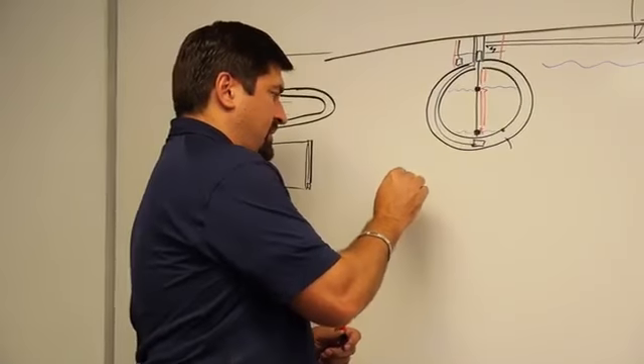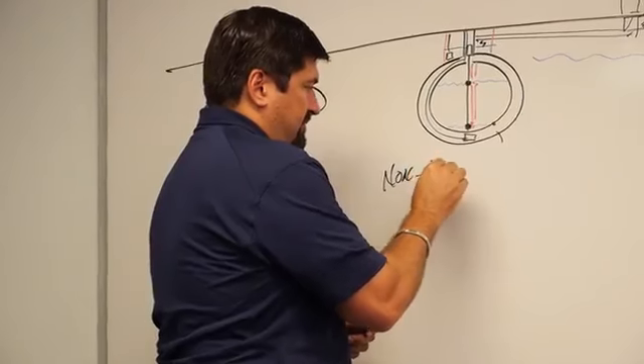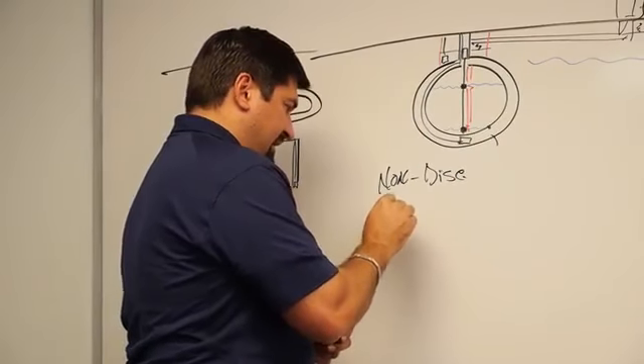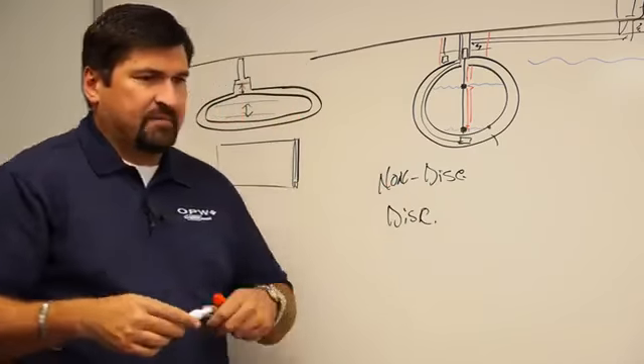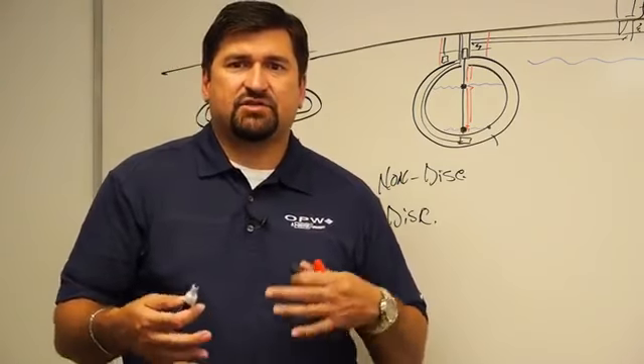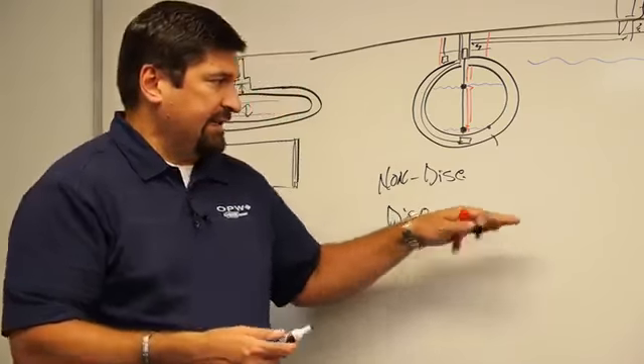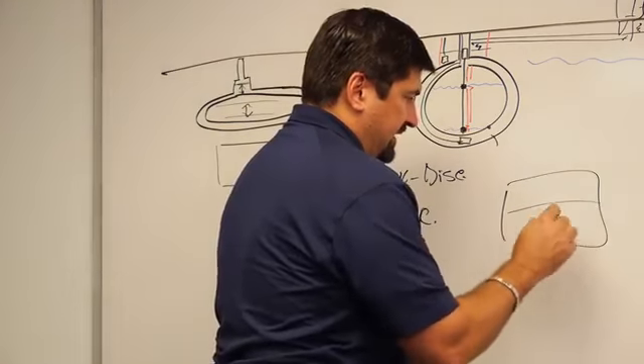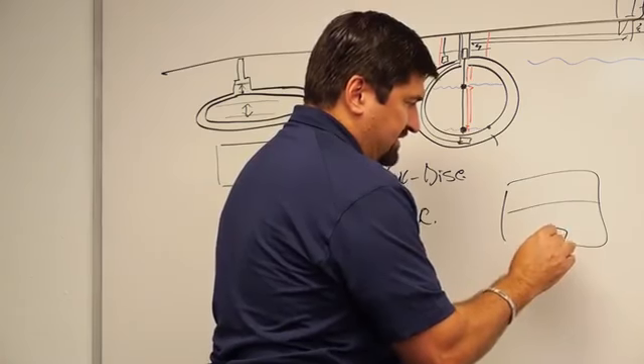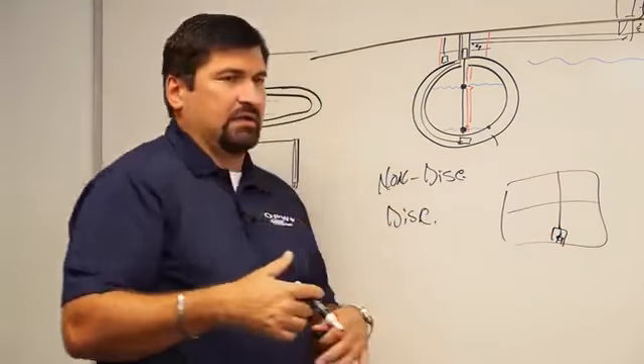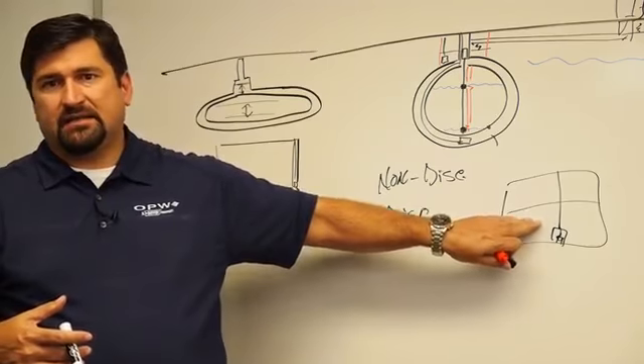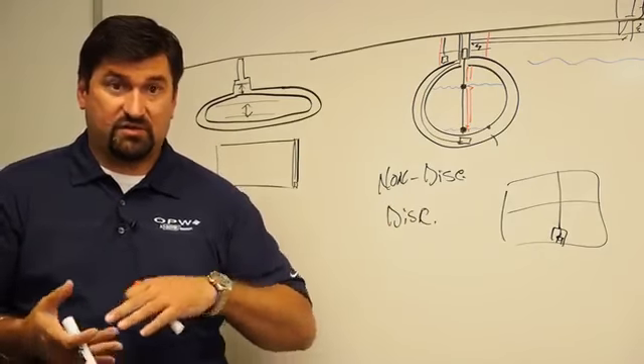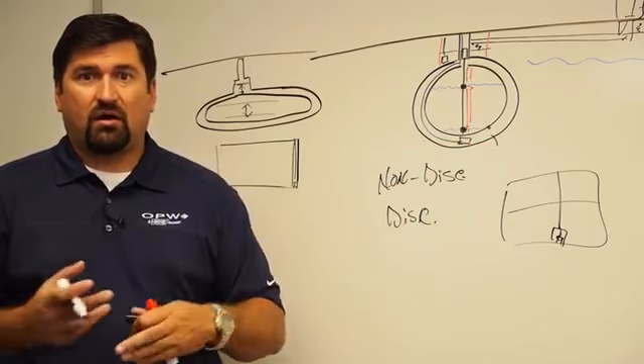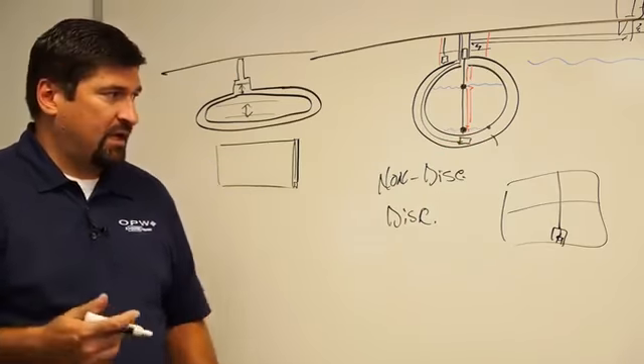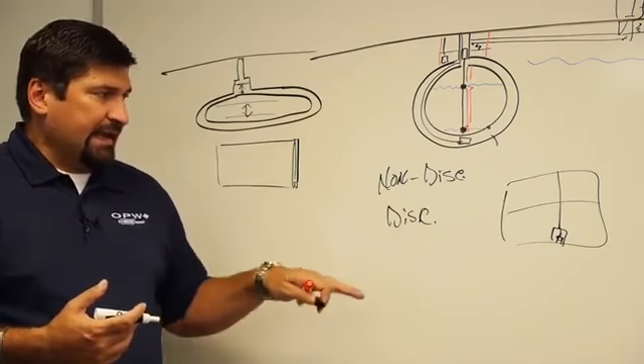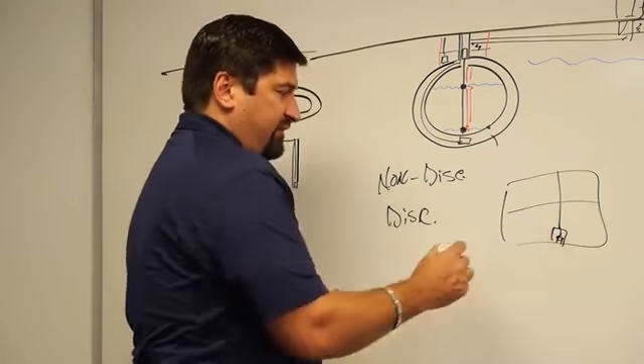There's non-discriminating sensors and discriminating sensors. A non-discriminating sensor is just that. It's strictly a float type device that when any type of liquid is inside the containment, there's a little float on the inside that raises up, setting off an alarm, letting you know that there's some type of liquid inside this area, whether it be an STP sump or a dispenser pan, a monitoring well, or a reservoir through a transition sump.